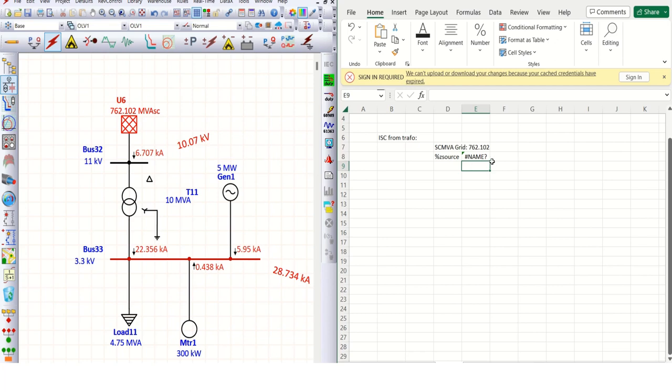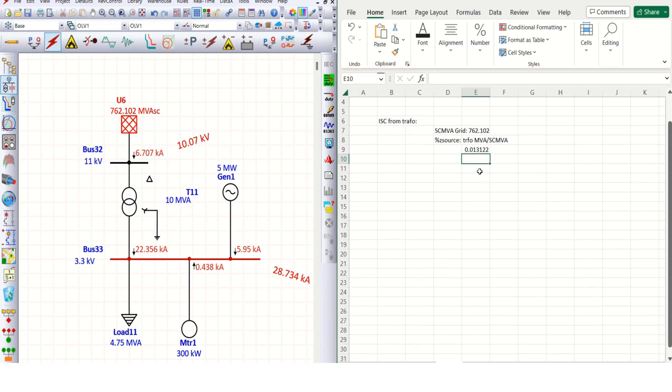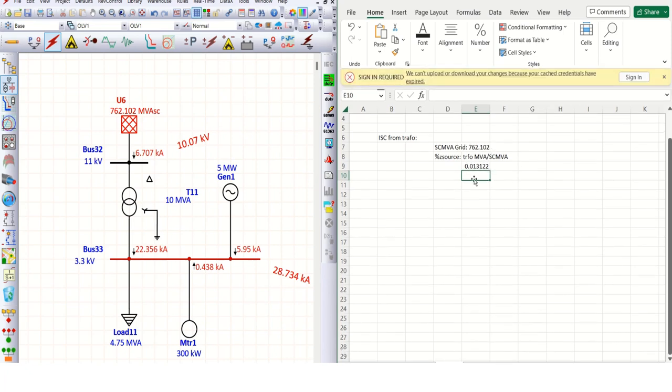So your percentage impedance is going to be 10 MVA divided by 762.102. This value is 0.013122. It is in terms of percentage, so go for multiplication by 100. So it is going to be 1.312 in terms of percentage. So source impedance has been calculated.